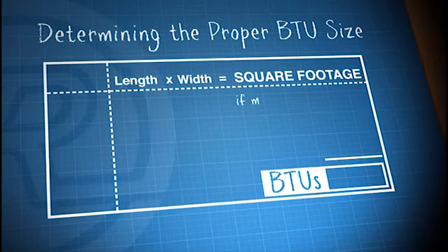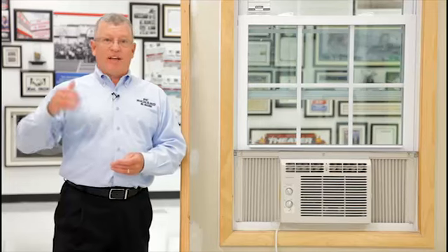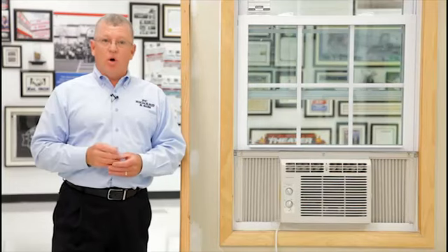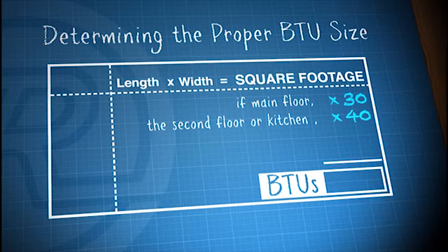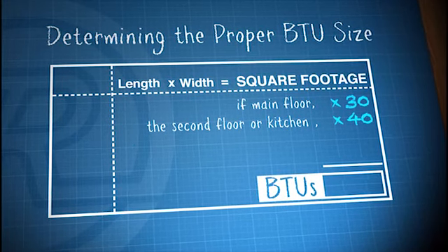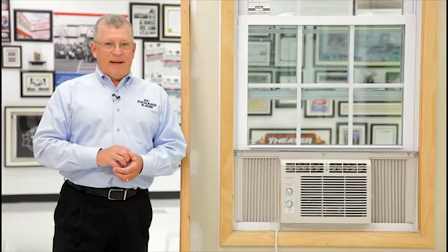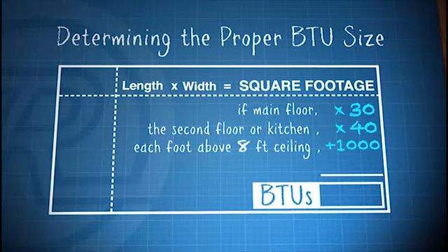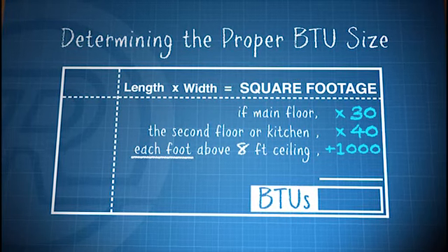If it's on the main floor, you'll multiply the square footage by 30. If it's a second floor or a kitchen area, multiply that square footage of the room by 40. If your ceiling height is over 8 feet, I always recommend adding 1,000 BTU for every foot over that 8-foot ceiling height.